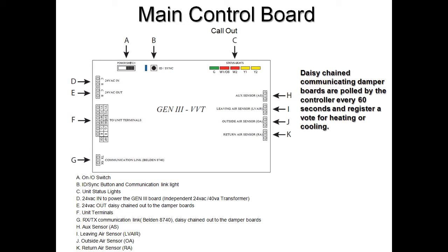The controller inputs include legacy-style connections to the RTU or split system, either gas electric or heat pump. 24-volt power in and a 24-volt power out terminal to daisy chain power, along with the TX and RX terminals, which carry the RS-485 communications loop, which are daisy chained to each damper in the system with no home runs back to the GenIII panel. Leaving air and return air wiring terminals, along with outside air, are included on the GenIII controller.